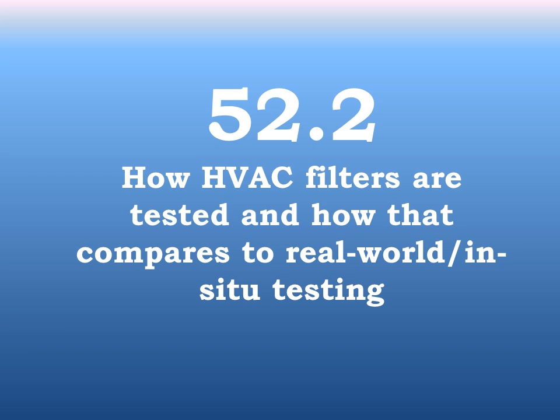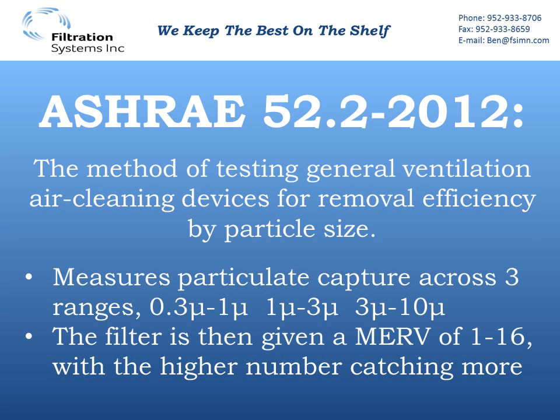ASHRAE 52.2 is the current test method for rating HVAC filters' particle capture efficiency. The 2012 revision is the most current. It measures particle capture across three size ranges: 0.3 to 1 microns, 1 to 3 microns, and 3 to 10 microns. The filter is then given a MERV of 1 to 16, with the higher number being the more efficient.